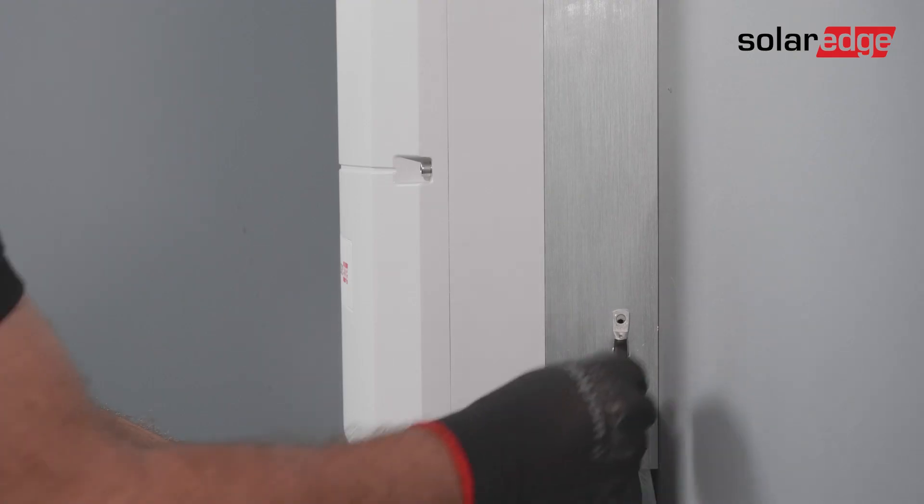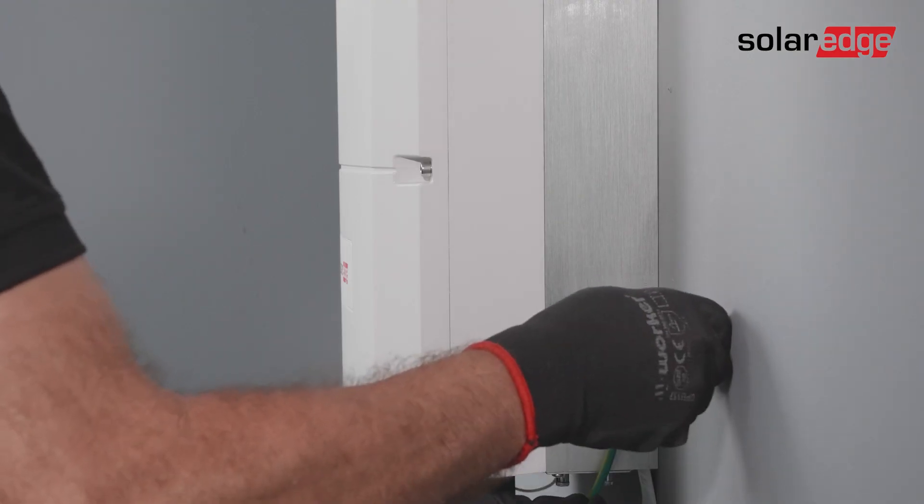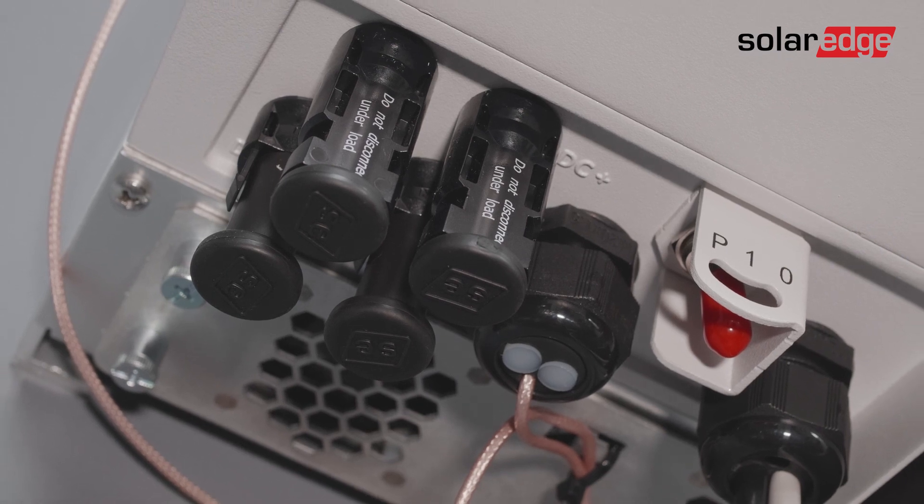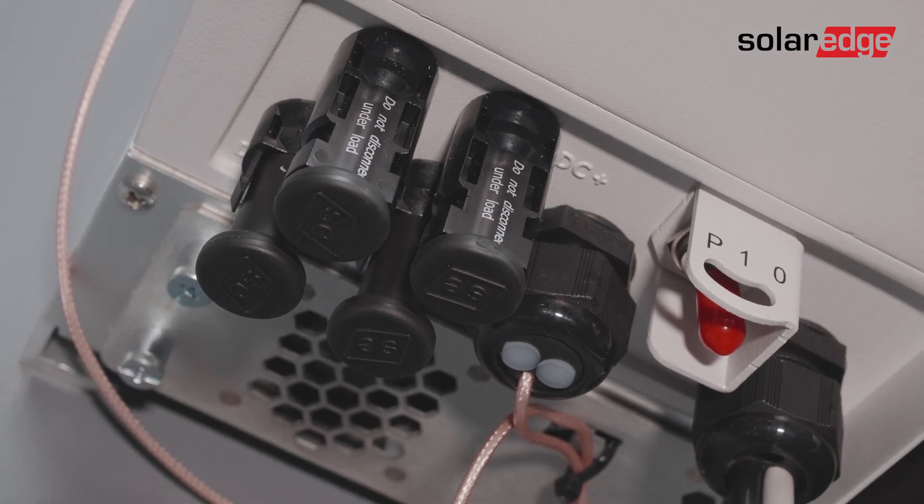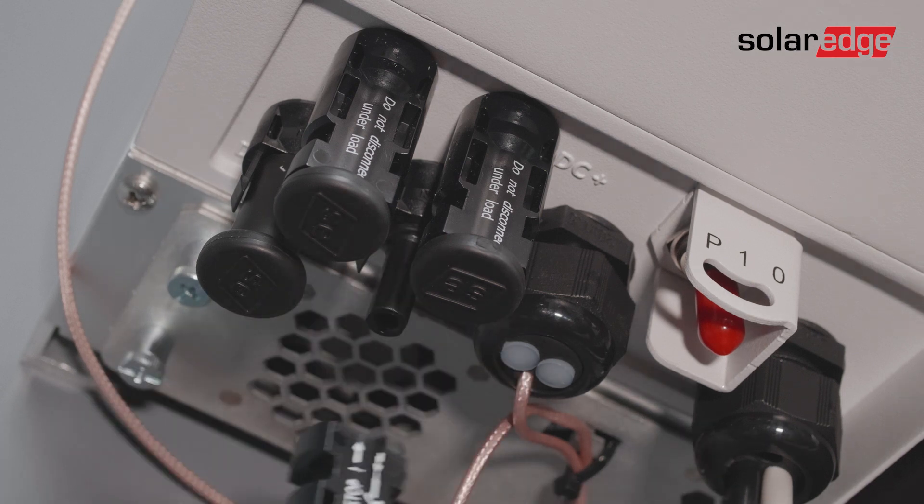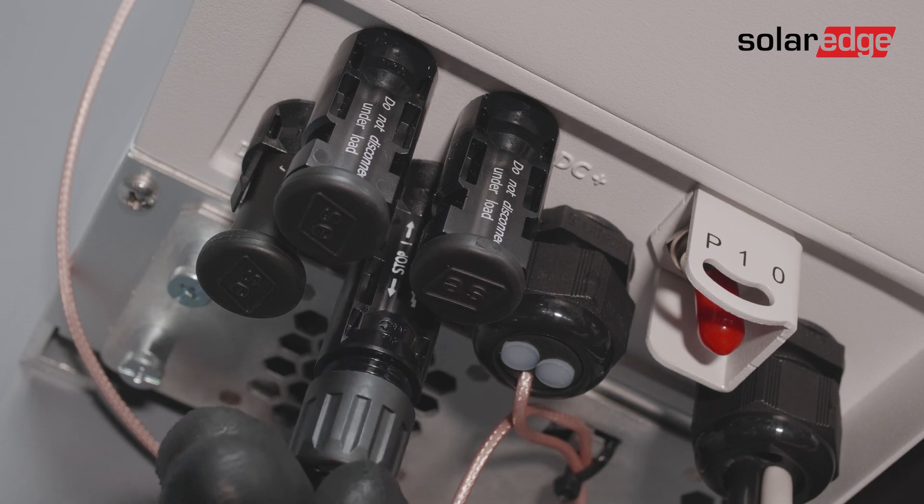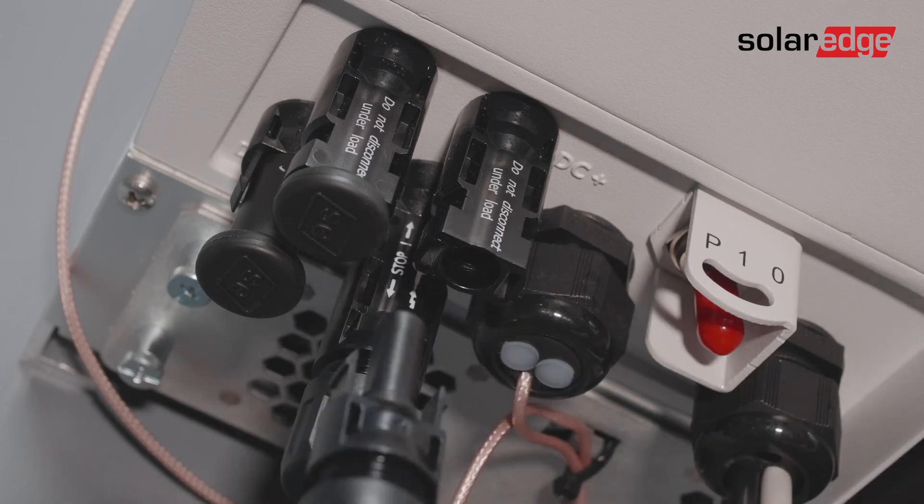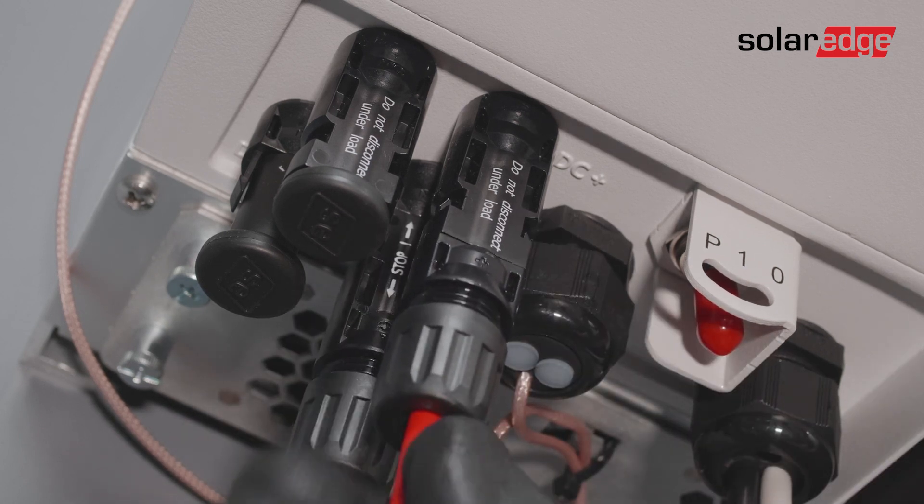Connect the grounding cable between the inverter and the battery. Now, connect the string to the DC input pairs. Please note the polarity. Connect the DC connectors of each string to the DC minus and DC plus connectors until you hear a clicking sound.